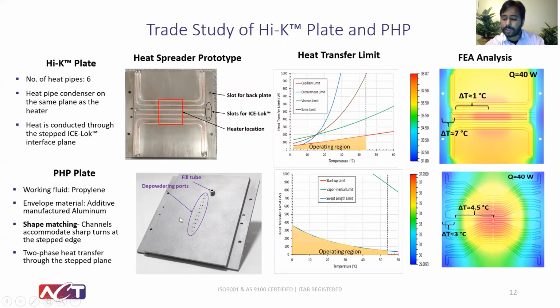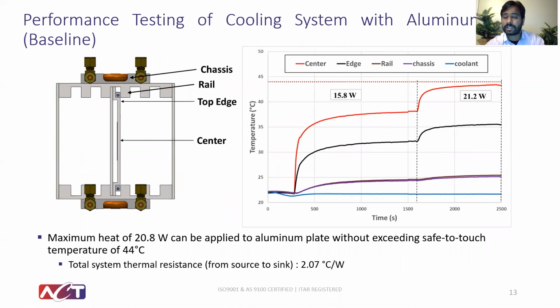In the case of PHP, the unique feature here is shape matching, which means we have the two-phase capillary channels extending along the stepped plane. So the delta T along the stepped plane is actually lower than the case of the high K plate.